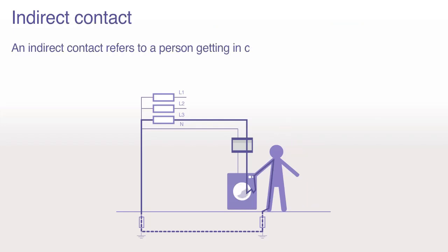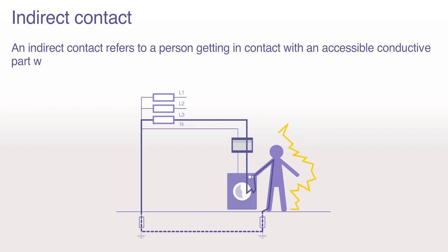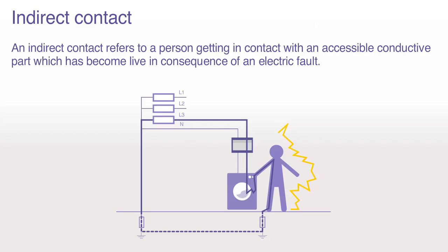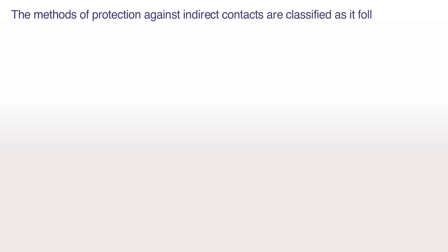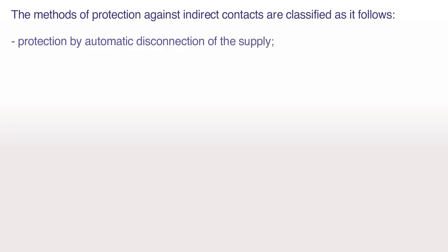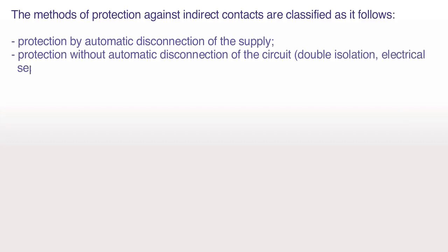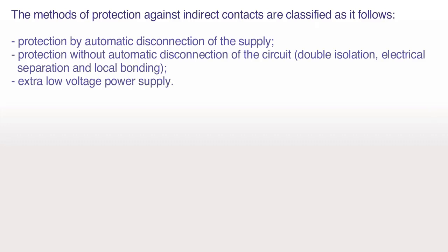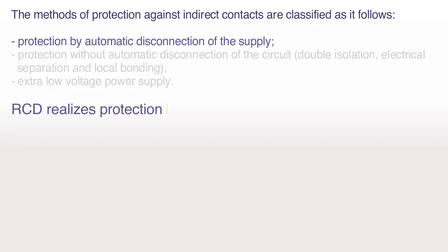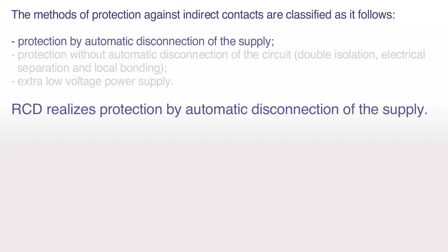Indirect contact. An indirect contact refers to a person getting in contact with an accessible conductive part which has become live in consequence of an electric fault. The methods of protection against indirect contacts are classified as follows. Protection by automatic disconnection of the supply. Protection without automatic disconnection of the circuit, double isolation, electrical separation and local bonding. Extra low voltage power supply. RCD realizes protection by automatic disconnection of the supply.